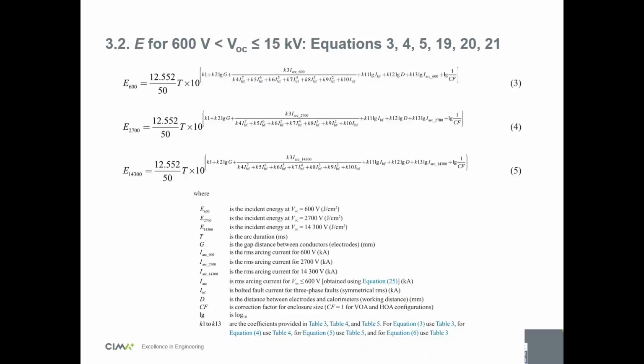So you need to calculate 3 energies, one at 600 volts, one at 2700 volts, and one at 14.3 kV. So regardless of your actual voltage, you need to calculate all of these. So if you're at 480 volts, well, this is a bad example because it's below 600 volts, these equations only. So let's say you're at 4.16 kV. You need to calculate energy at 600, energy at 2700, and energy at 14.3 kV still.